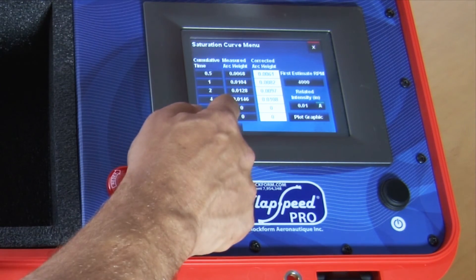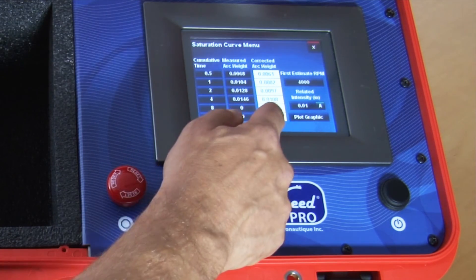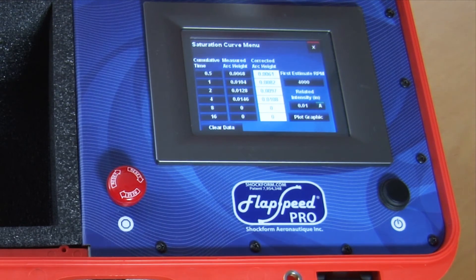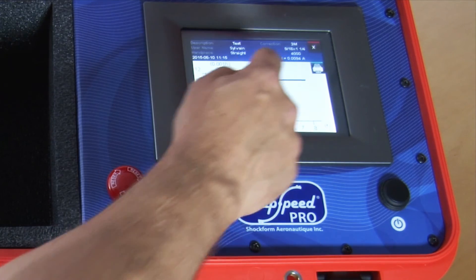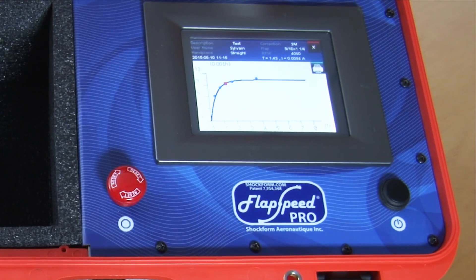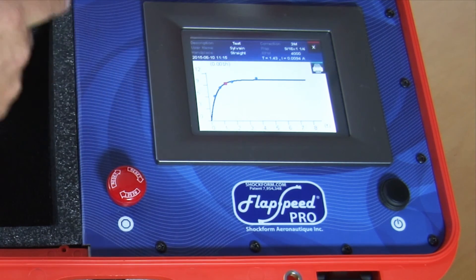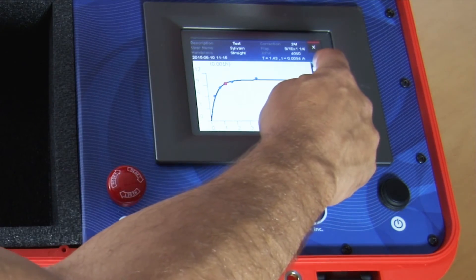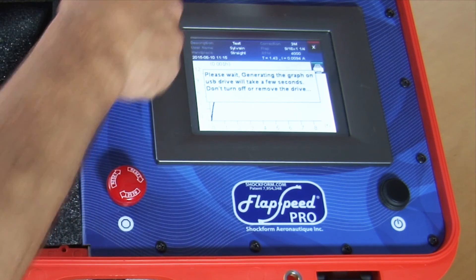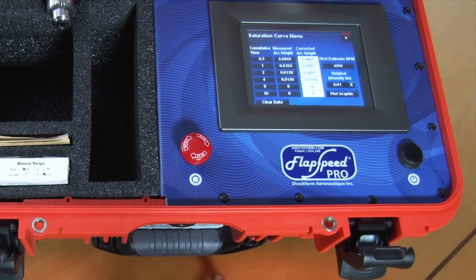Now you see that the measured arc heights are here in this column, and the system automatically corrects them because we're using a magnetic holder. We've got at least four points, so now we can do plot graphic. We're getting an intensity of 0.0094 at a time of 1.43 minutes, and we have a nice saturation curve. We press the print button and that sends it up to the USB key. Now we're done with our saturation curve — we're happy with the intensity and ready to work on the part.